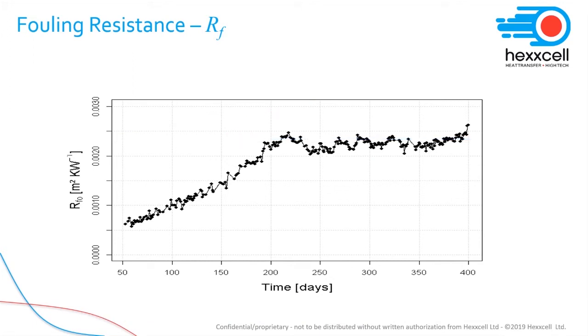From a monitoring point of view, this graph is commonly used by operators to assess the performance of the heat exchanger, the amount of fouling build-up, and to detect potential problems. For example, in this case, some people may look at the trends and use a linear extrapolation to represent the expected behavior of the heat exchanger. Once the measured value diverges from this extrapolation, they may infer that there is a change in the fouling behavior and may take operating decisions accordingly.